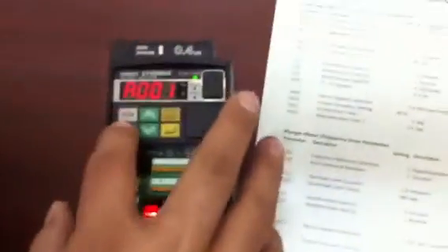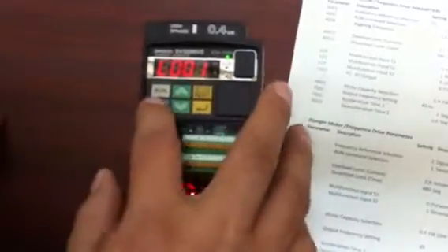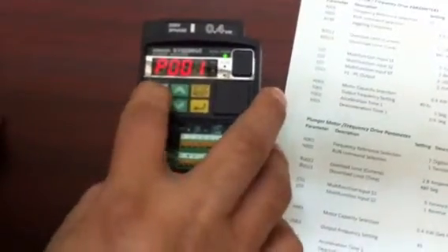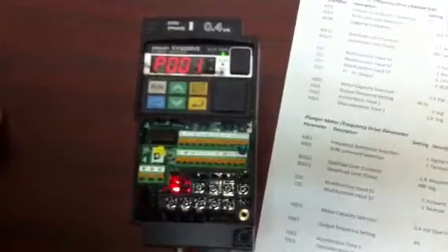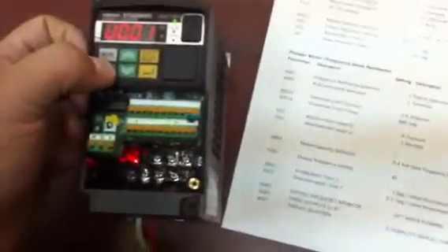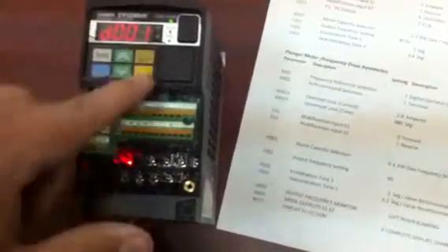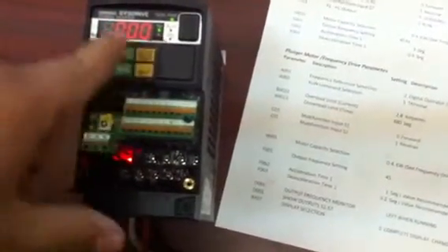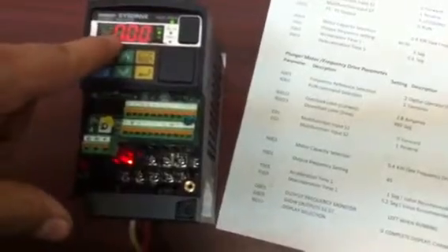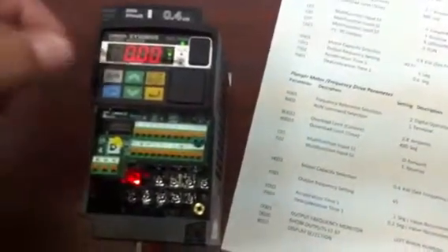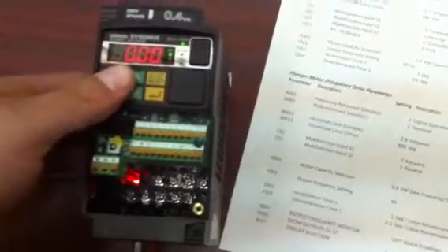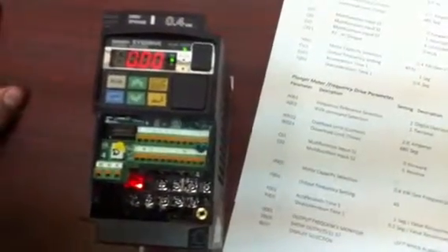The configuration for the plunger is very similar to this. You just need to make sure when you're going to run this for the plunger, use different parameters also defined in this sheet. One of the things I used to put in the parameter when it's going to run, so leave it at D001 and press enter, so it's going to show the frequency, our actual speed, which the frequency drive is sending to the motor to move.